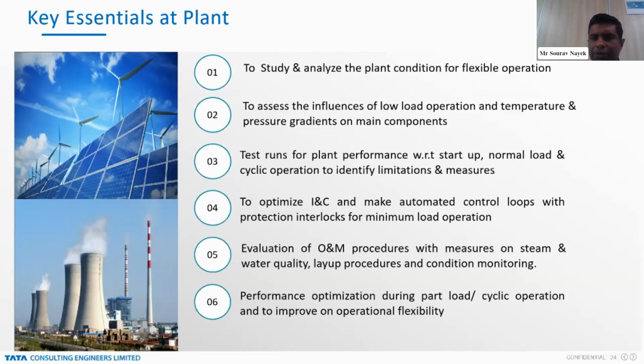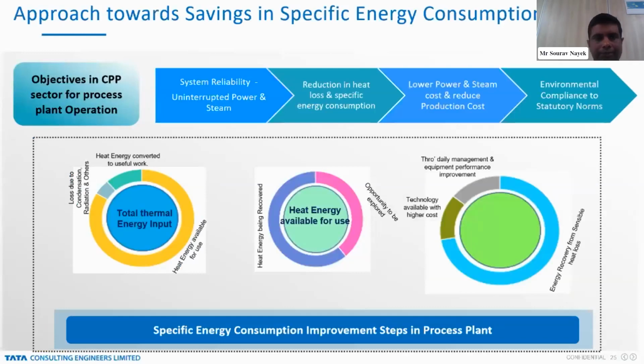Some O&M procedures also have to be optimized, considering the steam water quality, layup procedures, and the condition monitoring of the equipment. The performance optimization during part load and cyclic operation also should be looked into, because our main objective during flexible operation is to improve our heat rate. There should not be too much deviation, as we showed in the last slide. It is varying almost 20 to 25% in the thermal power plant. This we should minimize, and we should take measures for this.